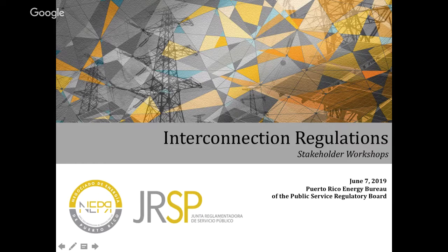So what is the mechanism that the Electric Power Authority has to ascertain whether that battery doesn't export to the grid? Because there are controls for an island to be created downstream from the Electric Power Authority, so the utility can say that they're not exporting from the battery. They may be able to export from the photovoltaic system, but not the battery. So the answer would be the battery has some controls—we're talking about communication functions. The equipment's brain tells the battery that when the authority isn't available, it's not allowed to export. Now, when the authority is there, it cannot export either. What the battery can do is supply the various charges that the system needs.